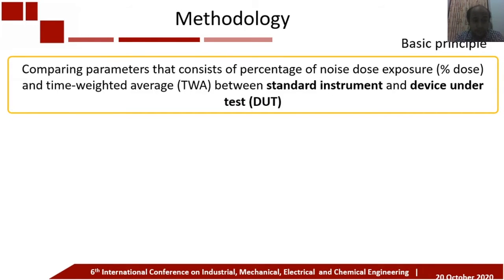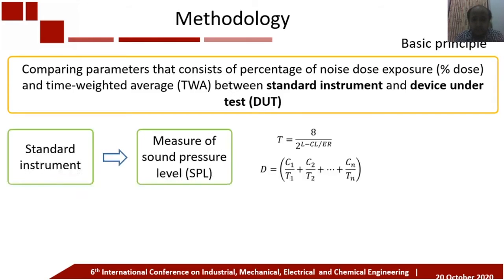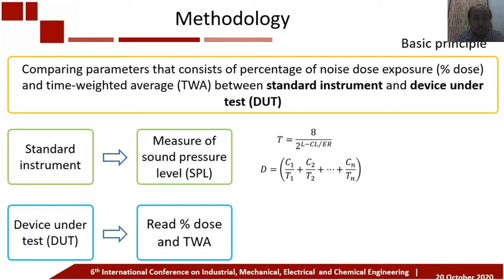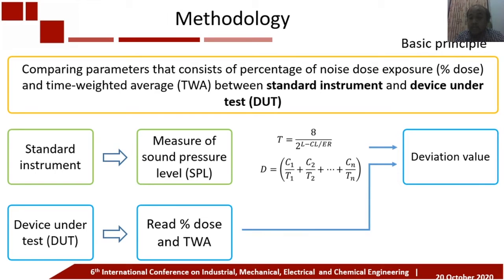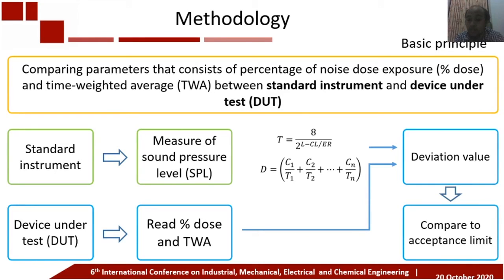Basically, this calibration can be conducted by comparing parameters between the standard instrument and the device under test, or noise dosimeter. For the standard instrument, first we measure the sound pressure level, and after that this measurement will be converted to dose in unit percent. For the device under test, or DUT, it indicates or reads the percent dose and TWA parameters directly. From the measurements of both instruments, we get the deviation value, and from this deviation value we compare it to the acceptance limit required by the standard.